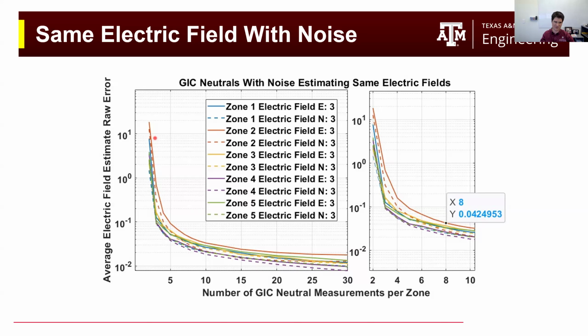This is a simulation, but the eventual goal is to do this in real time, or if you have GIC measurements coming in from the field, from your transformers, you can back-estimate the E field and then do a state estimation calculation of the GIC flows on parts of the system that don't have GIC measurement devices.